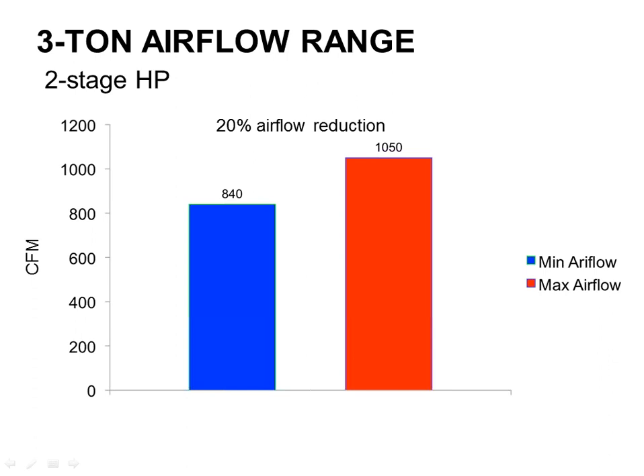This just shows you what happens on a normal 2-stage heat pump or air conditioner. So in this example, I'm running 1050 CFM for this 3-ton heat pump. When I run only one stage, I reduce the airflow down to about 840 CFM. Right, because I'm not really cutting the compressor speed in half. I'm only cutting him down from 100% down to like 80%. So I can only do the same thing with the airflow on the indoor unit.